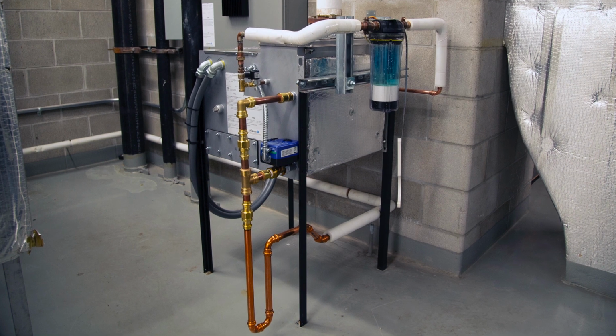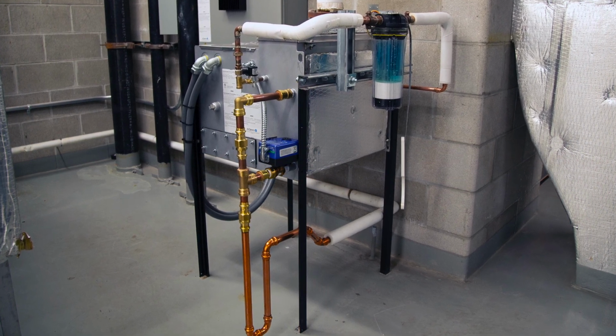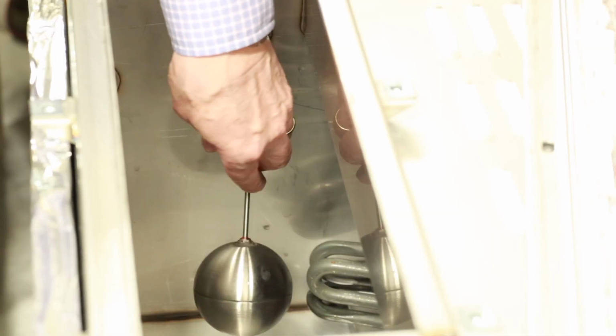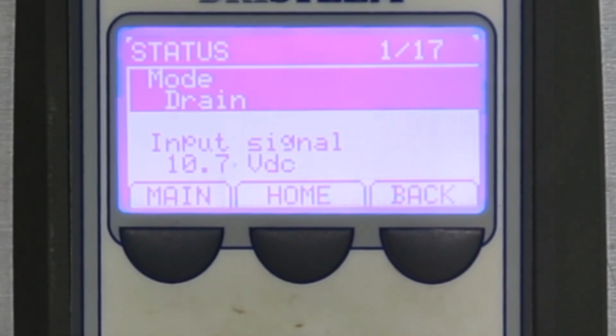Allow the humidifier to cycle through multiple fill cycles and verify that the humidifier cover, cleanout plate, and probe holder gasket are not leaking. For off-season maintenance, perform complete inspection and cleaning of the following: probe rods, skimmer port and water seal, humidifier tank, heaters, float valve, and low water cutoff switch for RO and DI humidifiers. After cleaning, the humidifier should remain empty until humidification is required.